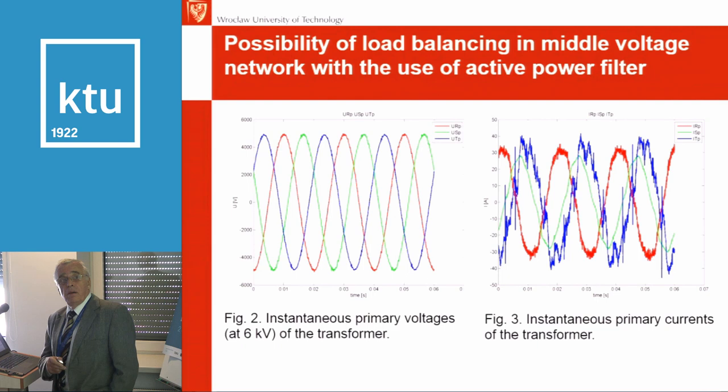We have a problem not only with asymmetry, the currents are not balanced, but also the waves are tremendously distorted. Therefore, we have high harmonics. High harmonics are not good, since they flow through the transformers, and transformers work like a filter. In this filter we have to dissipate energy, and very often the transformer is damaged. The power transformer is very expensive and should work about 20-30 years, but very often after 4 years it's already over. That's my main problem.